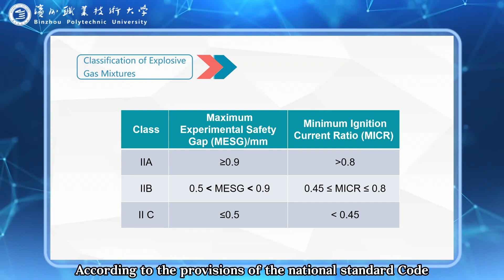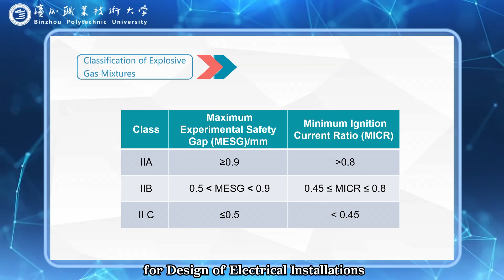How are explosive gas mixtures classified and grouped? According to the provisions of the National Standard Code for Design of Electrical Installations in Explosive Hazardous Environments, explosive gas mixtures are classified based on their maximum experimental safety gap, MESG, or minimum ignition current ratio, MICR, and grouped based on their ignition temperature.